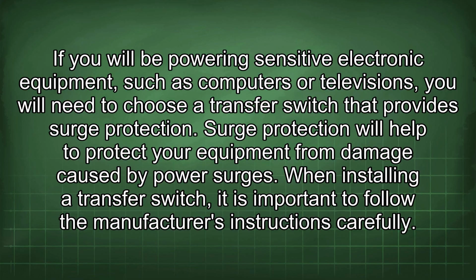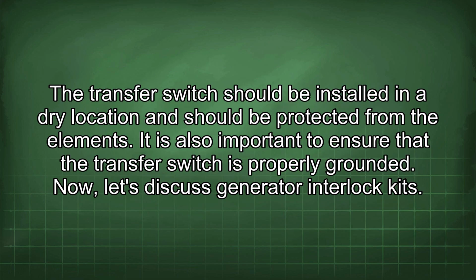When installing a transfer switch, it is important to follow the manufacturer's instructions carefully. The transfer switch should be installed in a dry location and should be protected from the elements. It is also important to ensure that the transfer switch is properly grounded. Now let's discuss generator interlock kits.